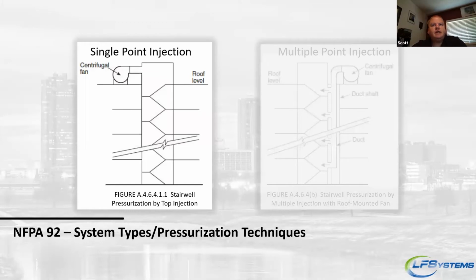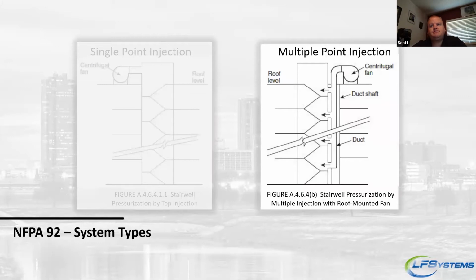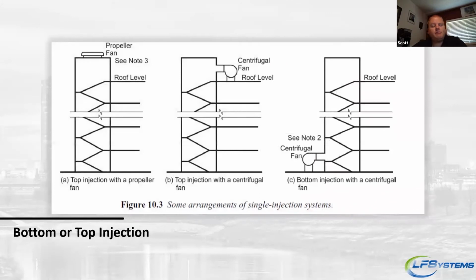Here are some system types for stairwell pressurization. There's single point injection, which is good for buildings up to about 100 feet, and then multi-point injection systems. On single point injection systems, there are several different ways. You can have a propeller fan on the roof, a centrifugal fan on the roof, or a centrifugal fan on ground level.